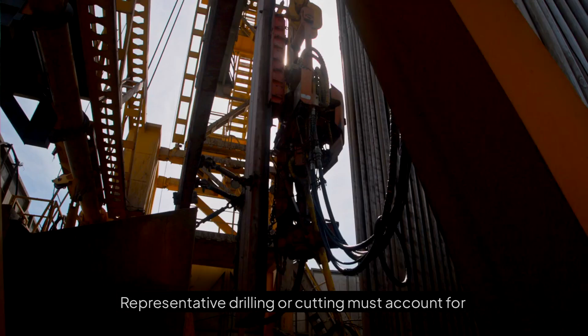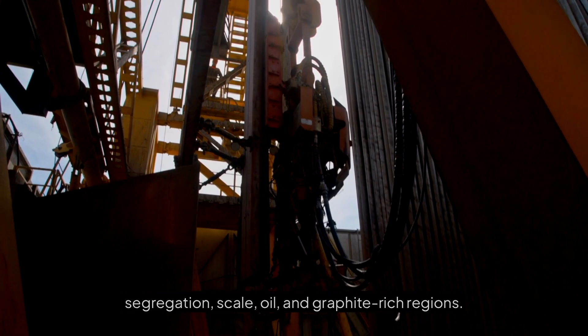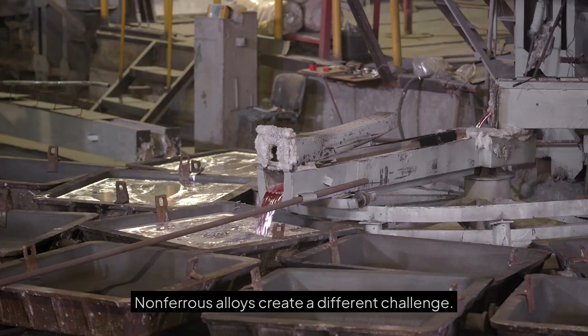Steel and cast iron are often relatively homogeneous, but preparation still matters. Representative drilling or cutting must account for segregation, scale, oil, and graphite-rich regions. Chill samples may not reflect bulk material, while inconsistent chip size can affect combustion behavior. Calibration should cover the grade families in production, using matrix-matched certified reference materials. Borderline carbon or sulfur values warrant repeat testing because they may influence grade assignment, machinability, inclusion behavior, or melt correction.